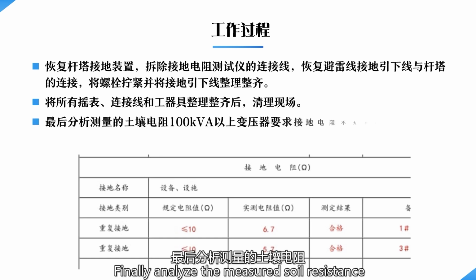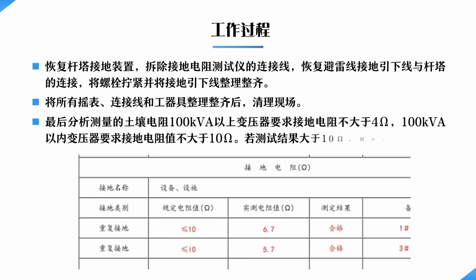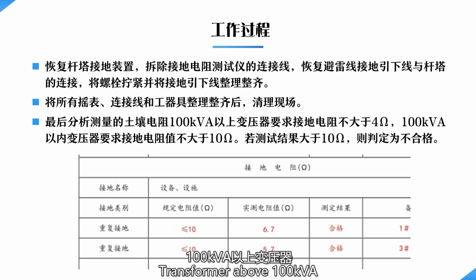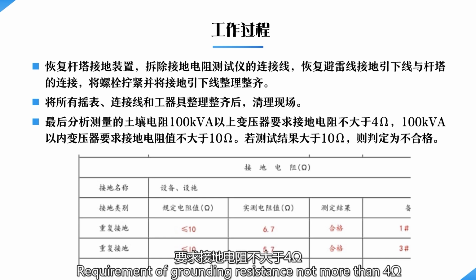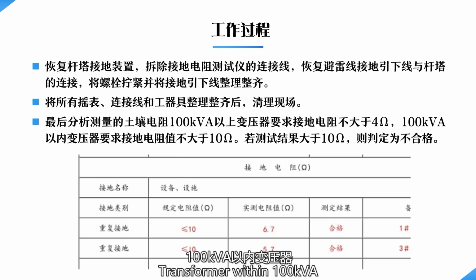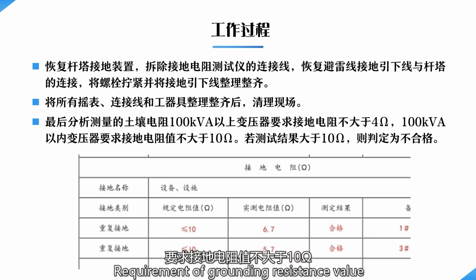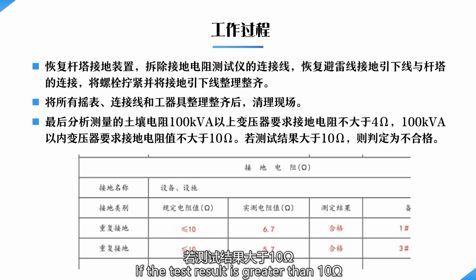Finally, analyze the measured soil resistance. For a transformer above 100 kilovolt amperes, the grounding resistance should not be more than 4 ohms. For a transformer within 100 kilovolt amperes, the grounding resistance value should not be more than 10 ohms. If the test result is greater than 10 ohms, it is judged to be unqualified.